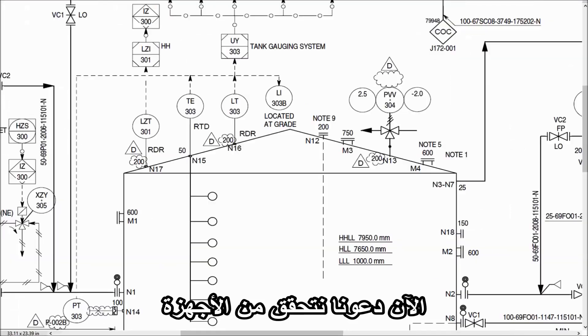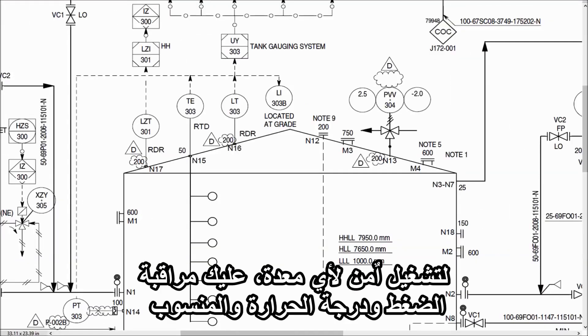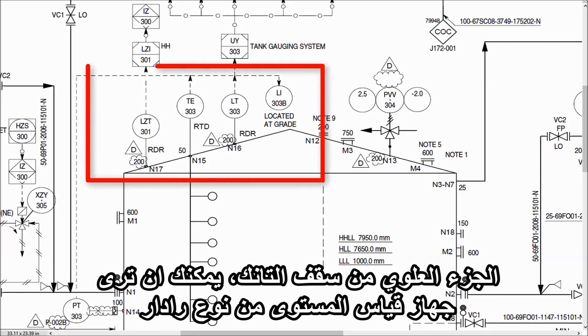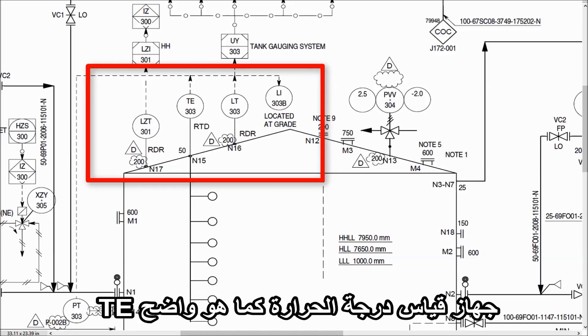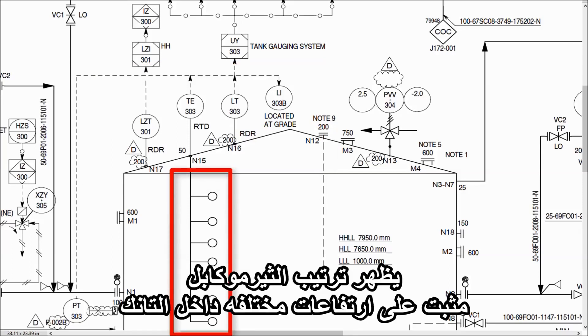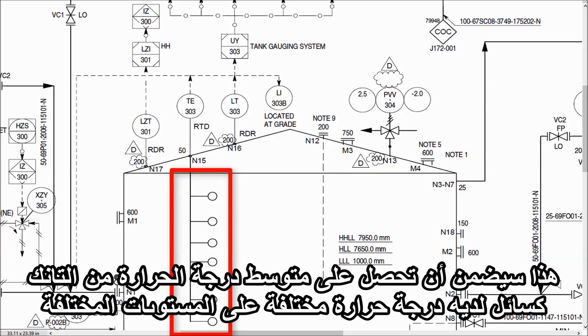Now let's check the instrumentation. For safe operation of any equipment, you have to monitor pressure, temperature, and level. Here you can see the pressure transmitter near the tank bottom plate. On the top of the roof, you can see the radar type level indicator and transmitter. The temperature gauge is shown as TE, which is the temperature element. This arrangement shows multiple thermocouples installed at different heights of the tank. This ensures you get an average temperature of the tank, as the liquid has a different temperature at different levels.